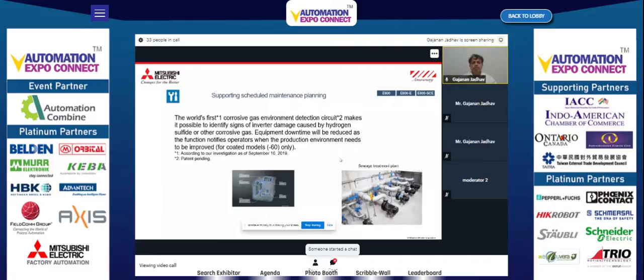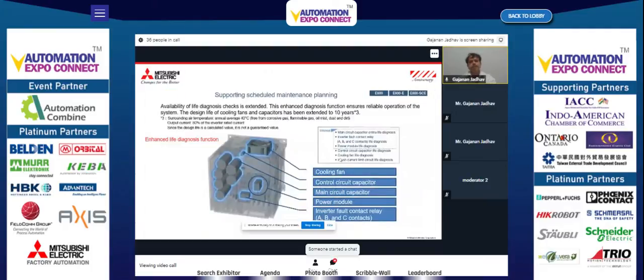This is the world's first corrosive gas environment detection circuit. Generally, there is always an argument when the drive gets faulty and arrives for repair. The repair people will say there is a corrosive environment, and the customer will never agree. But in this case, the drive will tell immediately if there is a corrosive environment. There are special sensors and special technology implemented in this drive, so immediately if there is a corrosive environment, it will give you alarms or alerts. We have applied for a patent, which is pending, for this technology.